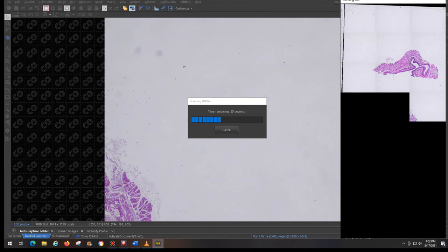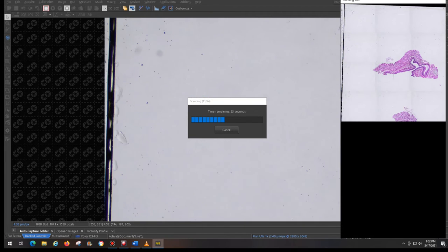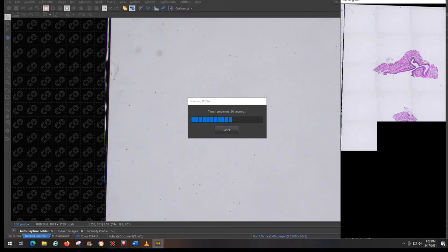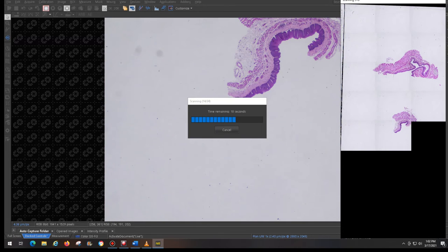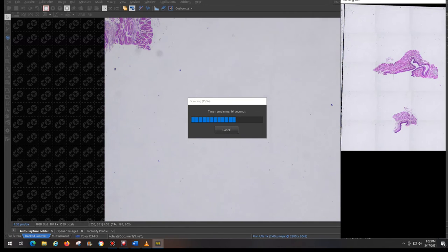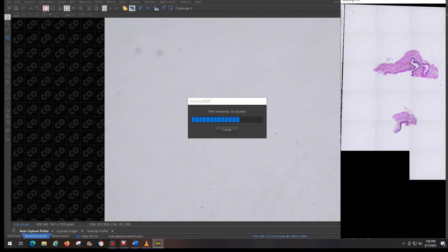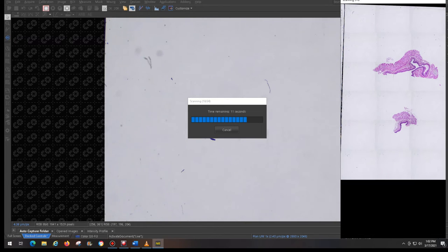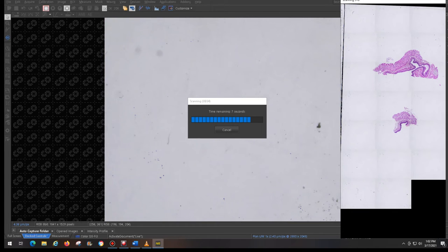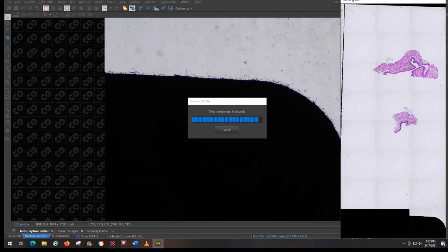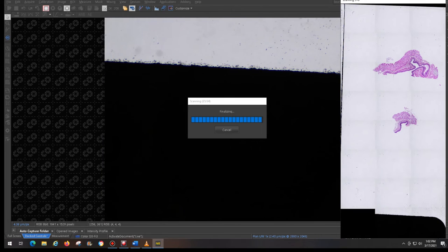Here we are scanning the working area of a 1x3-inch slide in real time. A 3x8 field scan will cover the area needed. The time from start to compiling the final image is 1 minute. The upper and lower borders of the image are the edge of the specimen holder and the slide label. As you can see, the lowest raster is mostly label, so we could eliminate the last row, bringing the total acquisition time to 48 seconds.